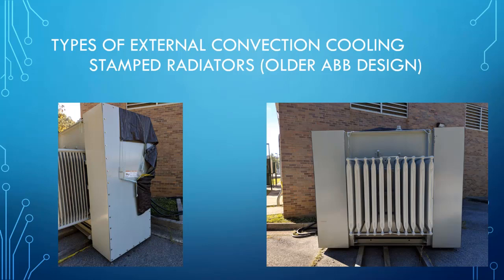So I ran across this transformer at a different water treatment plant. It's an older ABB unit, and this was a good design. ABB had the ability to manufacture these, we could call them stamped radiators. They manufactured them in-house, so they were able to provide a cost-effective method of cooling. A little better than corrugate, not as good as what I would call the pancake-style radiators, but very effective.